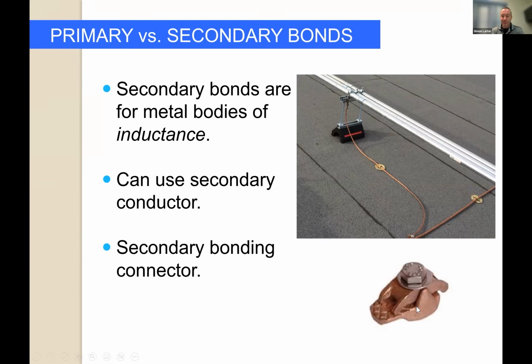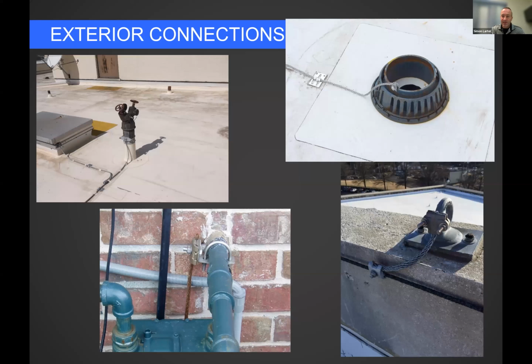And we use secondary bonding fittings. That's a picture of one down at the bottom. It's smaller, doesn't have as much contact area as a main bond would, but that's why it's secondary. Not intended for any current carrying. That's merely an equipotential bond. And here's some examples. That top right is a secondary bond. That's an aluminum secondary bonding conductor and fitting, just to that metal pipe there. The rest of these are all main-sized bonds.